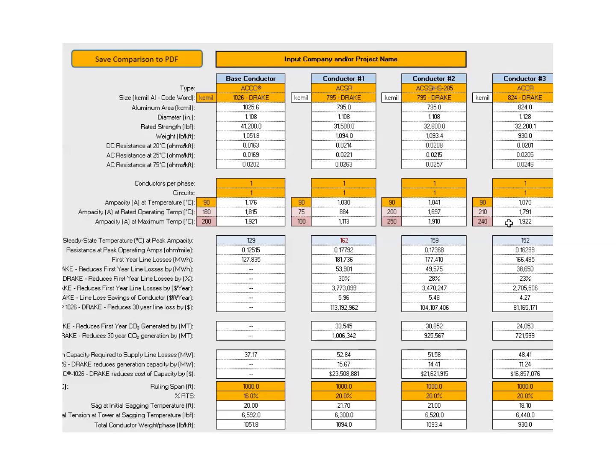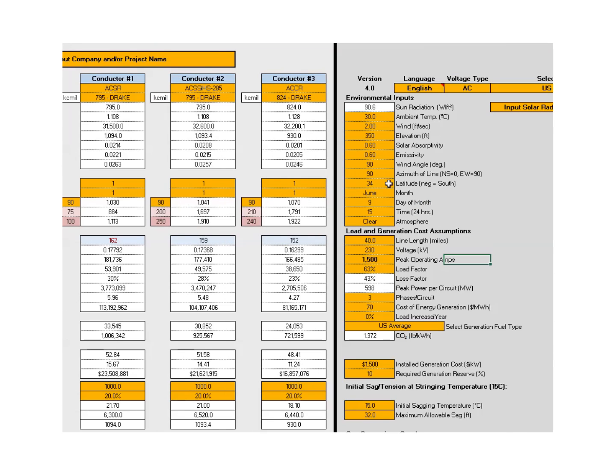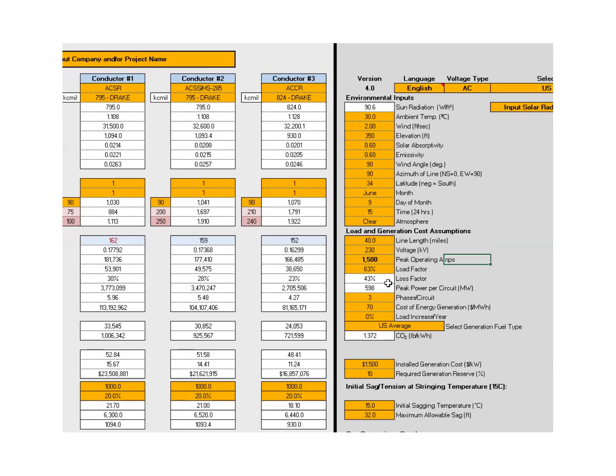So this is a program that can be used to compare any conductor size or type. It's very effective. The inputs are all based on IEEE 738 assumptions, the latest and greatest version of that. You can plug in all the variables, make sure that you use values that make sense. In other words, it's doubtful that you'd ever see a 100% load factor. So look at load factors, consider the voltage, the line length, and if you give it good input, it's very easy to compare things, including sag and tension, ampacity, and so forth.